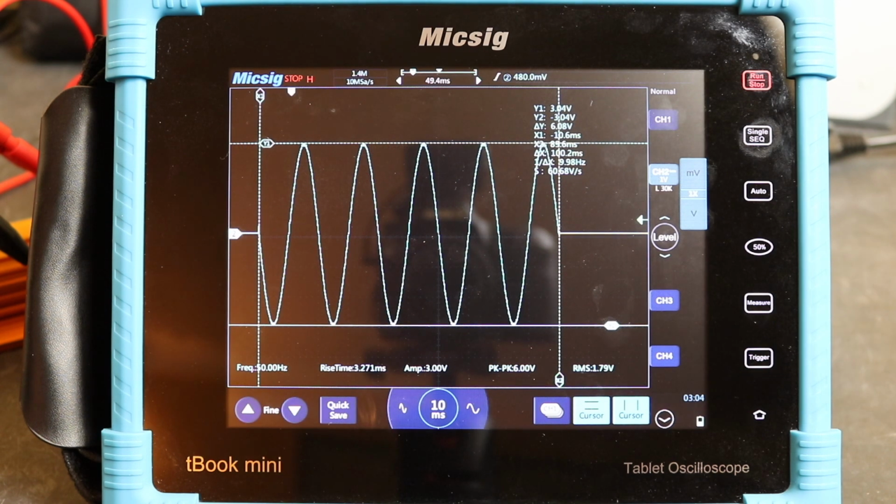Also taking into consideration that this scope has a 2% tolerance on the measurements on the voltage scale, so that adds to the equation a little bit as well. I think it will be okay to use this test set to test the performance of these current clamps with regards to their inrush measurement capability. It's just a good set of tests for me to do to get that confidence. But those measurements on those current clamps I'll put into another video, as this one's gone on for long enough now.